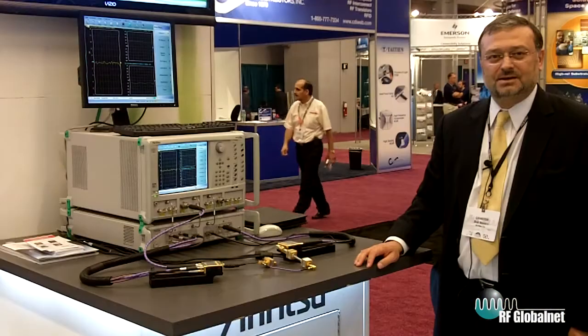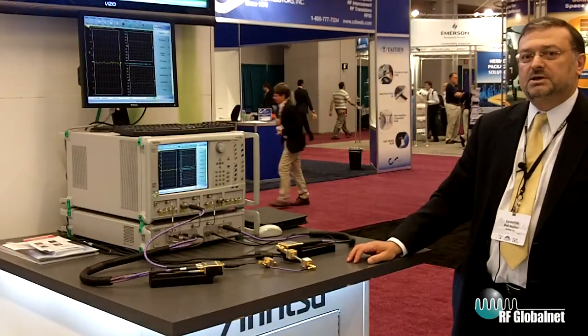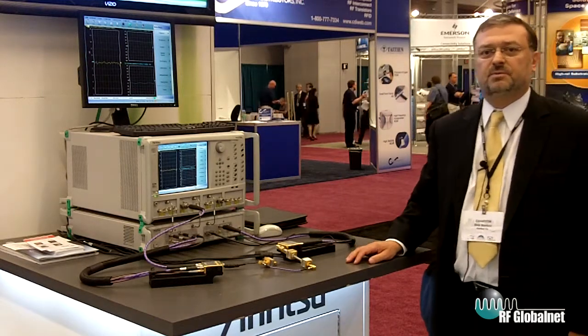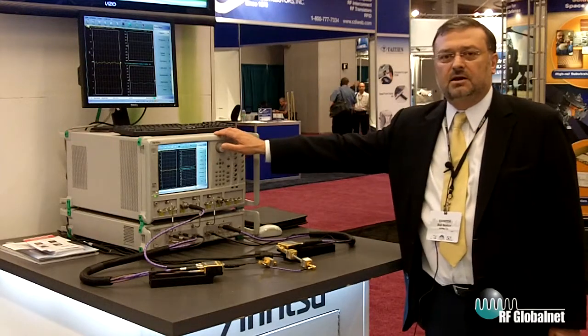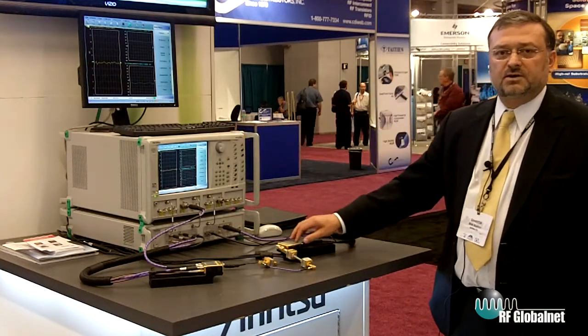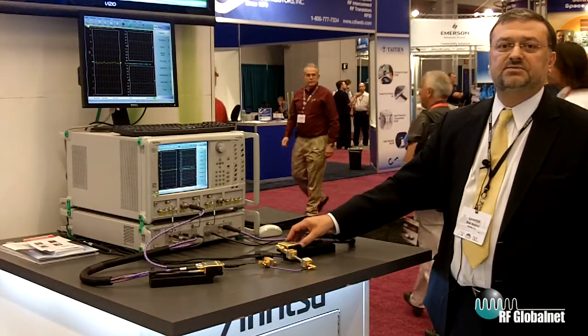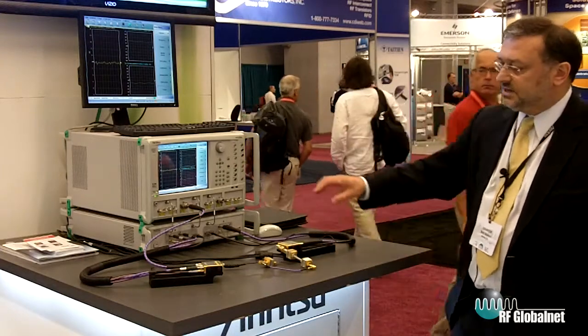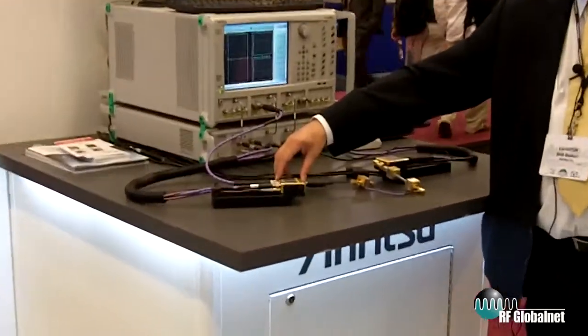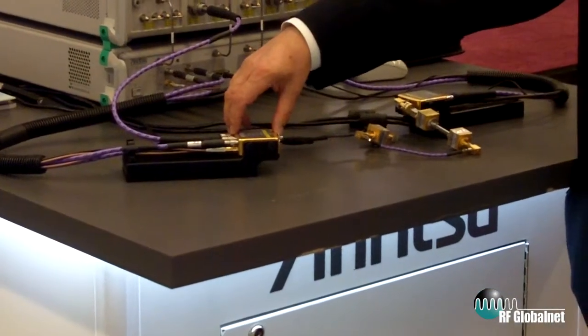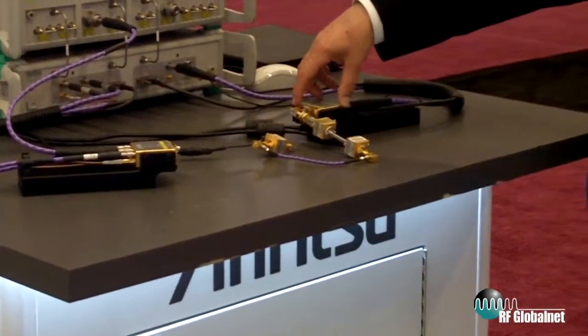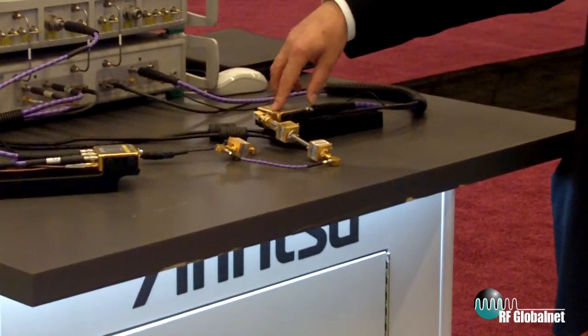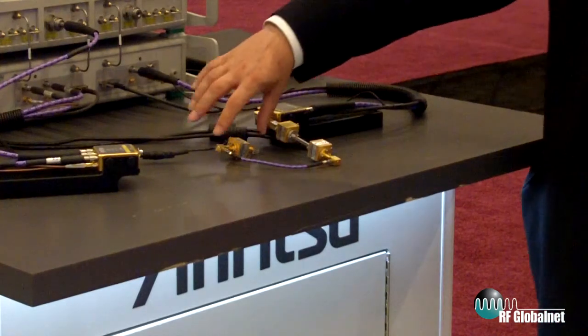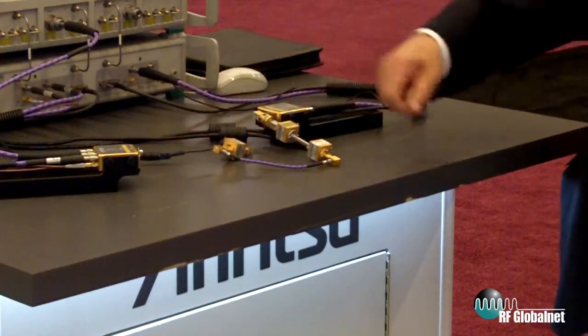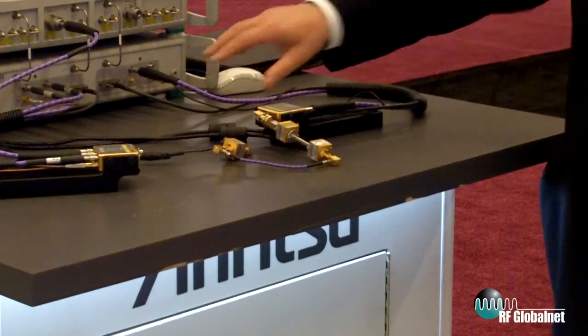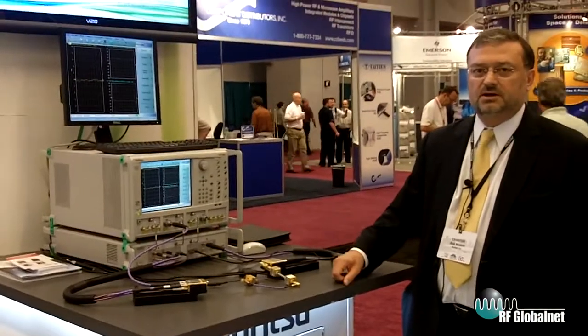Thank you very much. So here at IMS 2012, I'm very pleased to announce the introduction of a noise figure measurement system from Anritsu, again based on our VectorStar network analyzer, but as an industry first making noise figure measurements using a vector network analyzer to 125 gigahertz. We've achieved this by taking the modules that you've already seen, which are our modules that we use for broadband measurements to 110 gigahertz, and turning them into receive-only modules. By doing this, we get much lower noise figure from the module itself, and hence we're able to measure device noise figures down to 0.8 of a dB or less. Again, this is all the way up to 125 gigahertz, an industry first.